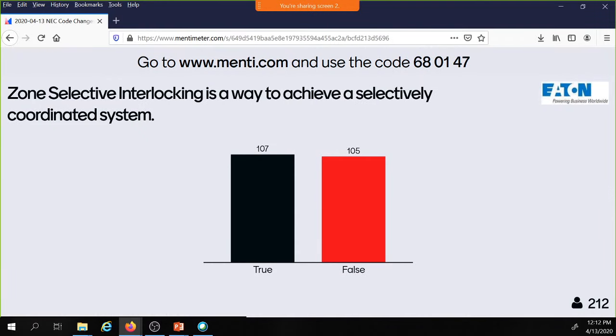Zone selective interlocking is a way to achieve a selectively coordinated system. At one time in my life, I know I am going to give a class, ask this question, and everybody's going to get it right, because I am going to have hit every engineer and contractor out there, and manufacturer, because I have heard some manufacturers say this wrong. Zone selective interlocking is not a way to achieve selectively coordinated system. Zone selective interlocking is there for incident energy reduction. And I know why people get this messed up. It is because of how we teach it.